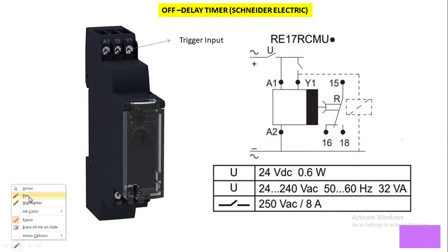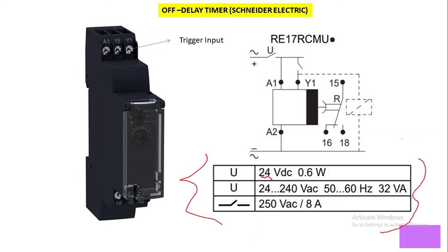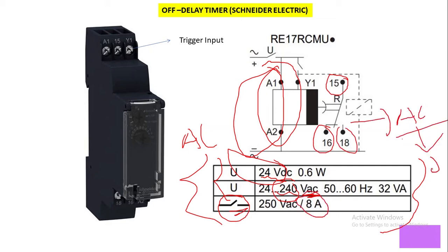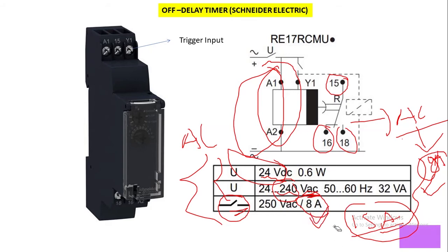For supply, we can apply 24 volt DC across the terminals, or 240 volt AC as well — both AC and DC are acceptable. The contacts can handle AC supply with a current capacity up to 8 ampere. If your load exceeds 8 ampere, say 15 ampere, you cannot connect it directly; you would first need to operate a contactor or additional relay.